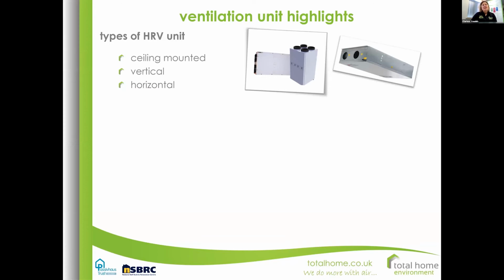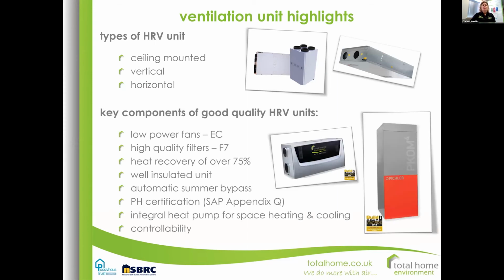So getting back to the ventilation unit, things to expect, a bit more on a practical side here. Units can be ceiling mounted. Mostly they'll be on the floor, either vertical, so a bit next to maybe a kitchen unit type situation, or you can mount them on a wall and still utilize the area below it. Key components to look out for, especially on those specification sheets, are low power fans, EC motors, electronically commutated.